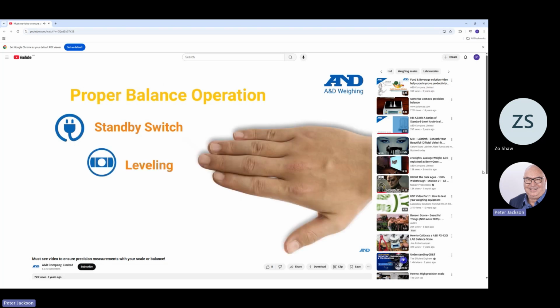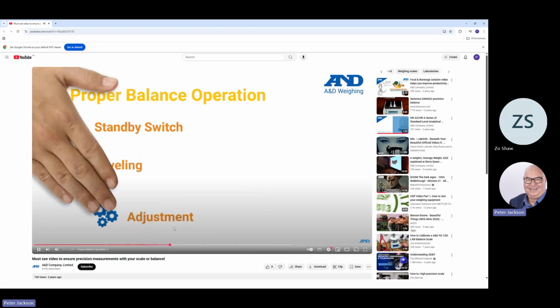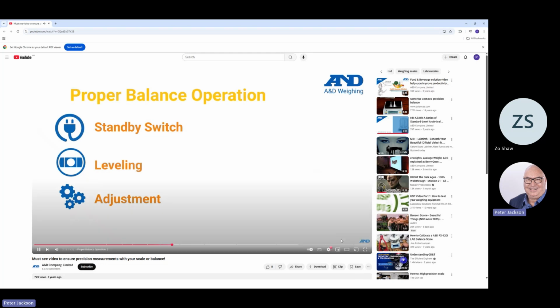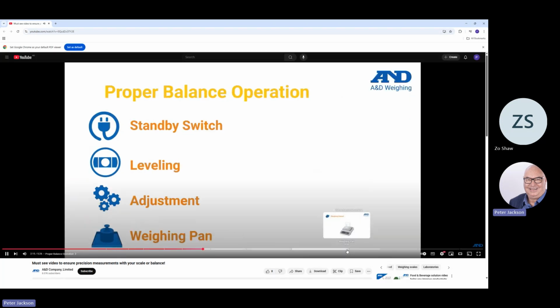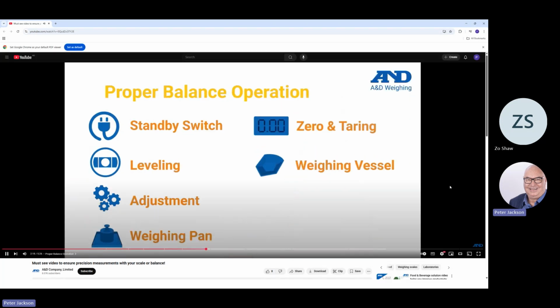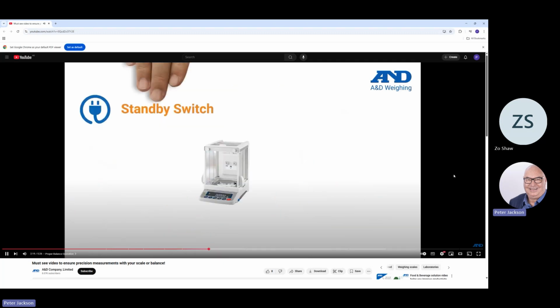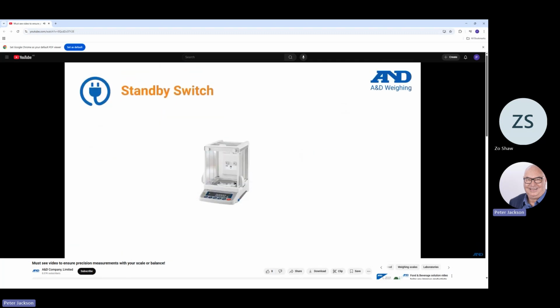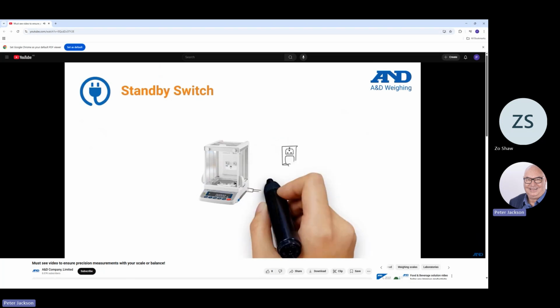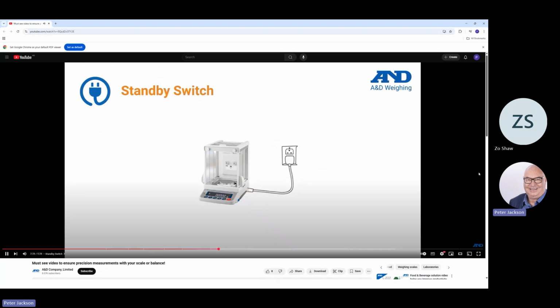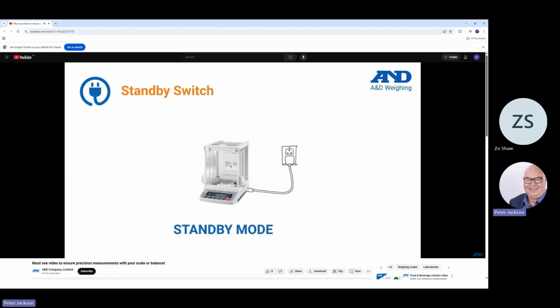First is the standby power switch. Next is balance leveling and also calibration adjustment. Then we will explain the relationship and importance of the weighing pan, zero and taring your weighing vessel, and properly cleaning your balance. The balance should always be connected to its power supply, and should be left in standby mode perpetually. The majority of A&D balances have standby modes and are designed to be powered all the time.